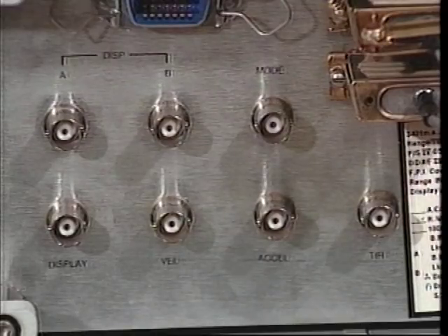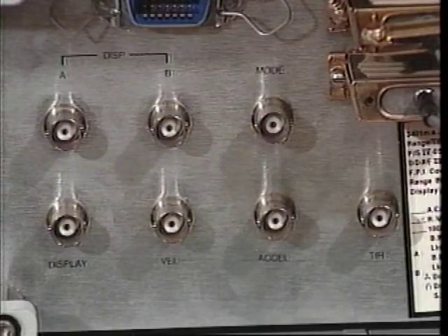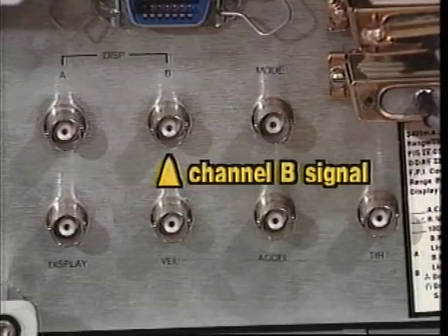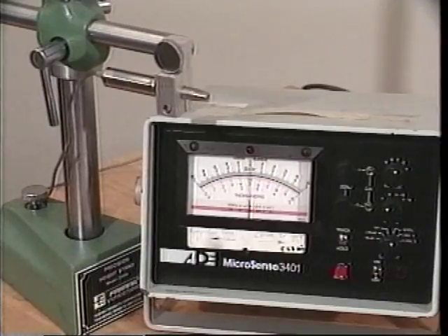The analog signal representing the measured displacement is plus or minus 10 volts with a scaling factor of 100 microinches per volt, regardless of the range selection. Auxiliary outputs allow differentiation of the displacement signal to obtain velocity and acceleration values. While cap gauges do offer many benefits, some disadvantages should be noted. For this particular unit, the nominal separation or working distance is 4/1000 of an inch.